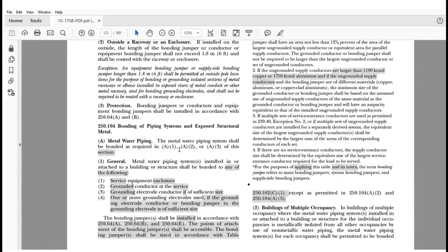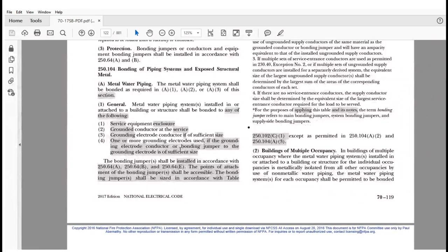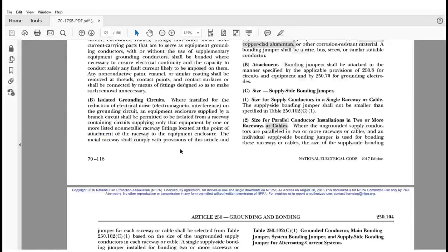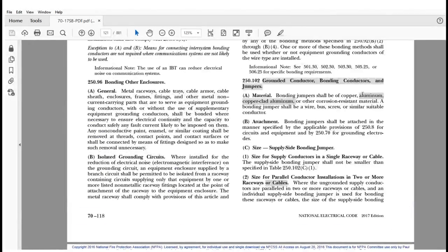What's the critical component that I want to add here is, let's go back to here. Look at these words here. Many people got confused when they read this and thought that only copper was corrosion resistant material. That is not the case. Aluminum and copper clad aluminum are very corrosion resistant materials. Very much so. In fact, they form a protective film on them that helps preserve them. So actually it's very self-preserving in those corrosive resistant locations.